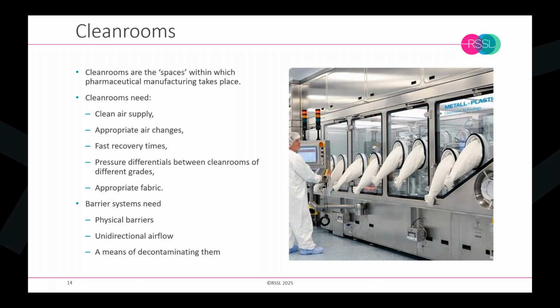So if we take the clean room, the auditor should be able to ask, what is the clean air supply rate? What is the extract rate? And what's the overall number of air changes within the room? Because this is fundamental to the suspension of contamination in the air and the rate at which it is removed. So what's the rationale for it? Why has this room got 10 air changes per hour? Why has another room got 25? What's the basis of that?